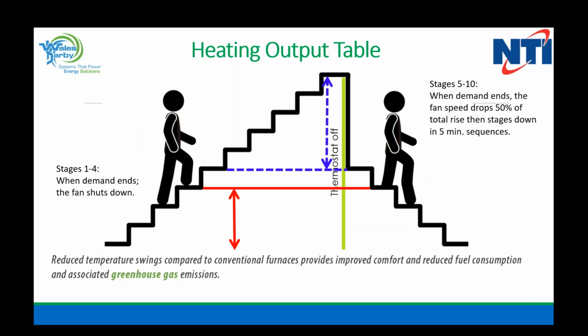So basically what happens is stages 1 through 4, when demand ends, the fan shuts down because that's such a small demand. It doesn't need to run at any level or continue to operate because it's about 50 CFMs per stage. So we're not really in a big hurry to get back to that level. We can get there relatively quick. But if we go anywhere between stage 5 and 10, when the demand ends, the fan will drop to 50% of the total rise in the stages for a 5-minute sequence. What that'll do is take any residual heat off of the coil and put it into the house. And this is all what gets us closer to that green technology.